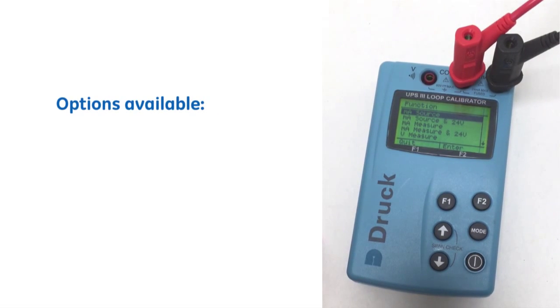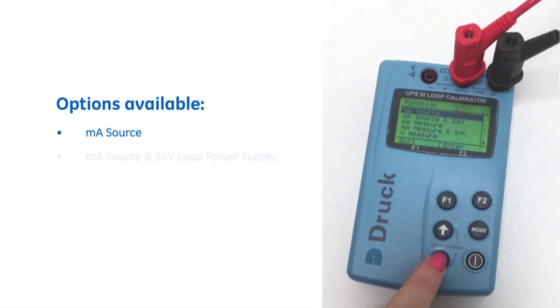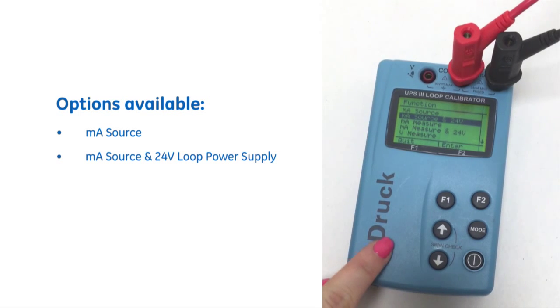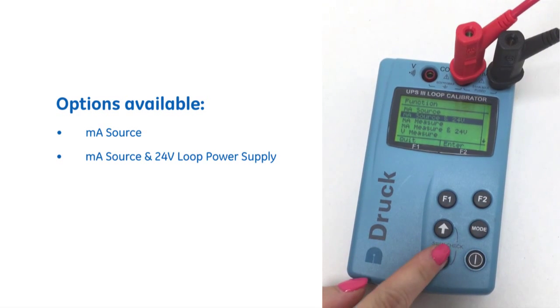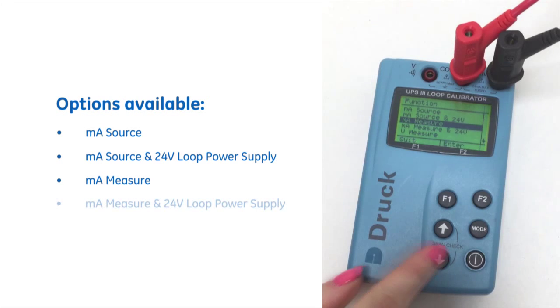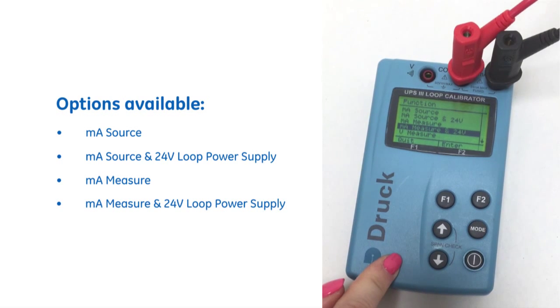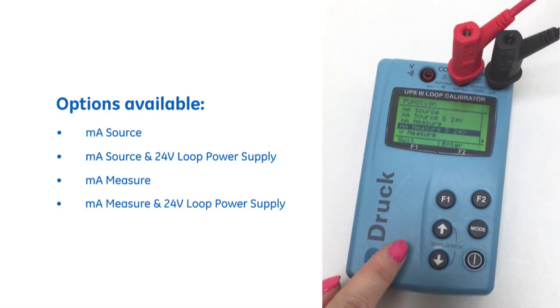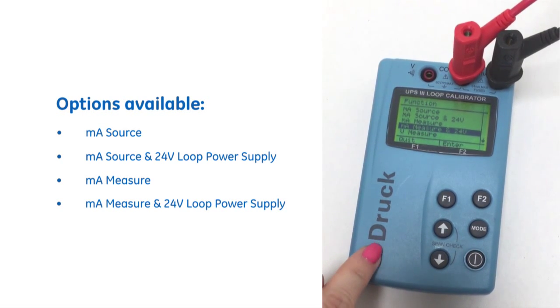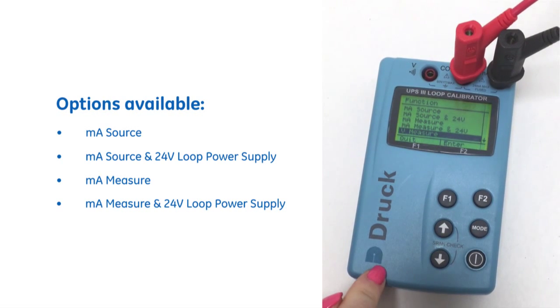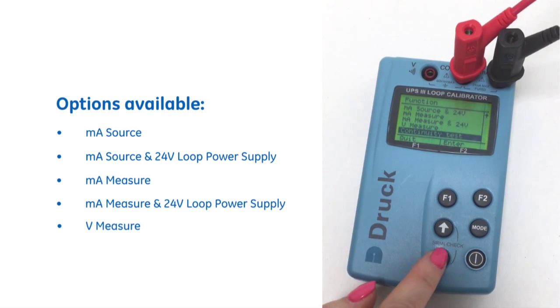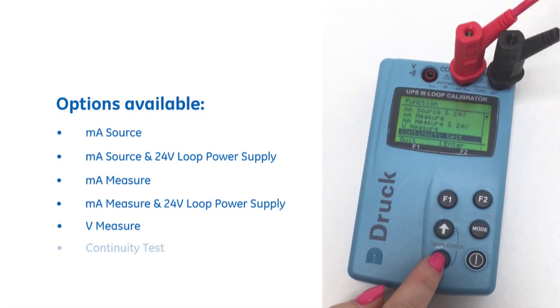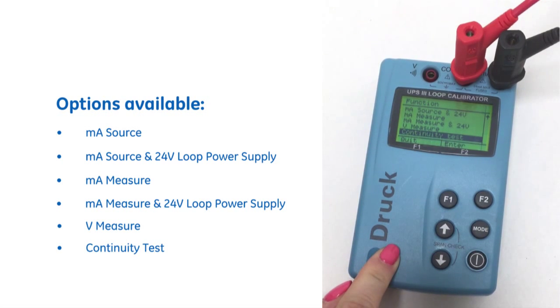we get the option to milliamp source, milliamp source with an internal 24 volt loop power supply, as well as milliamp measure and milliamp measure again using the inbuilt 24 volt power supply within the instrument. We also get the option to measure volts and do a continuity test, all in the one instrument.